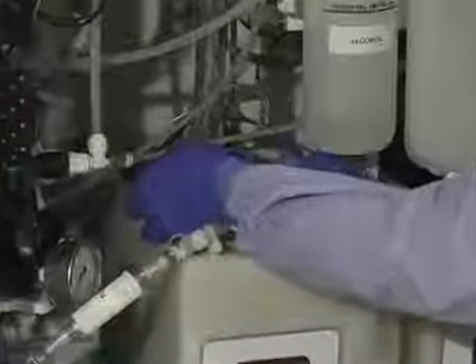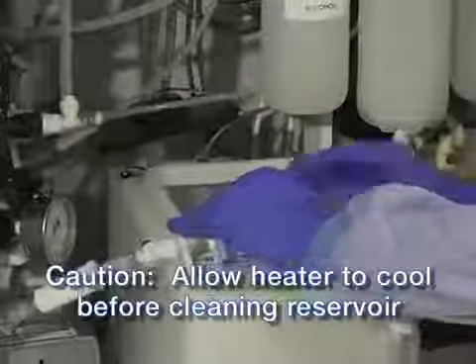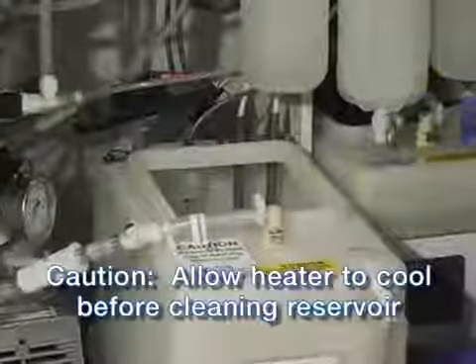The next step is to wipe out the disinfectant reservoir with a lint-free cloth. Remove the basin drain hose from the reservoir. Slide the reservoir out and remove the cover. Make sure that the heater has cooled sufficiently.